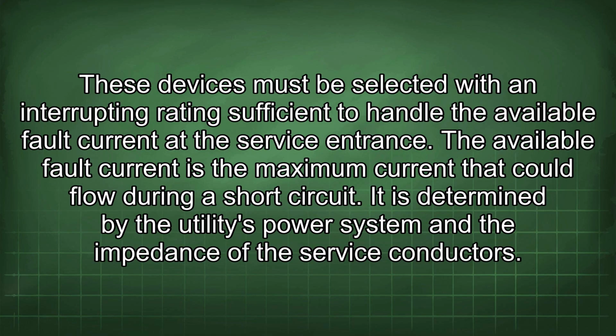These devices must be selected with an interrupting rating sufficient to handle the available fault current at the service entrance. The available fault current is the maximum current that could flow during a short circuit. It is determined by the utility's power system and the impedance of the service conductors.